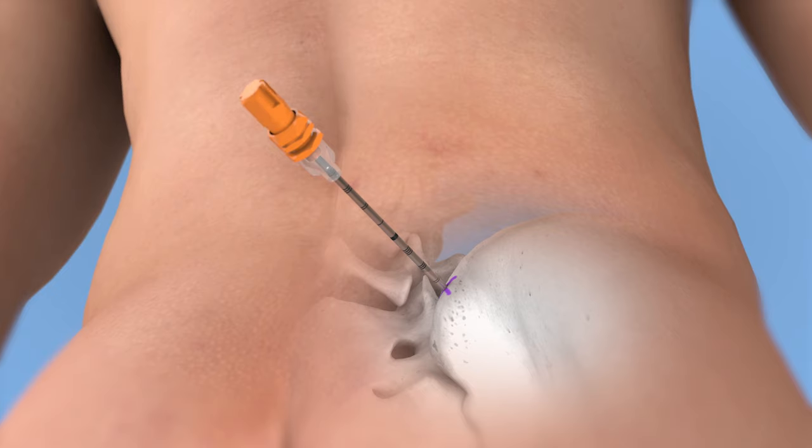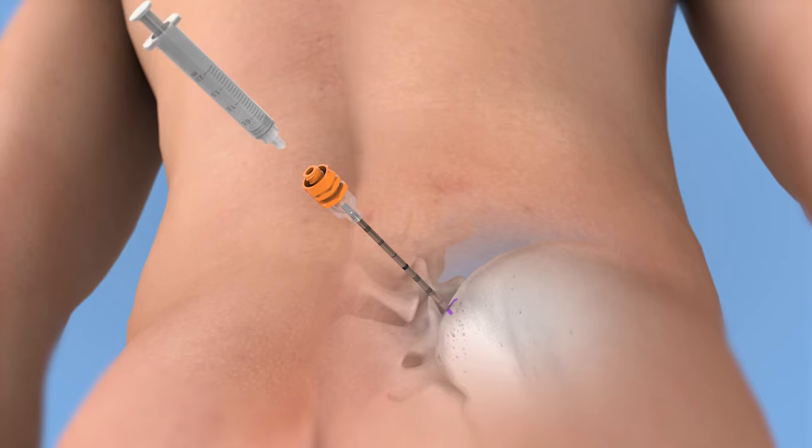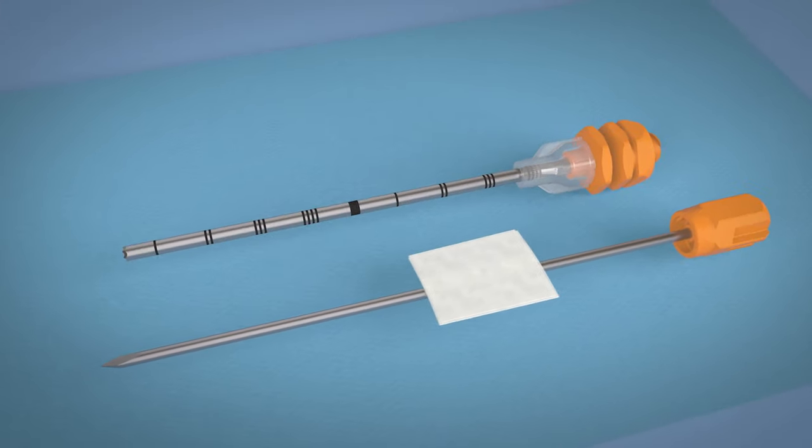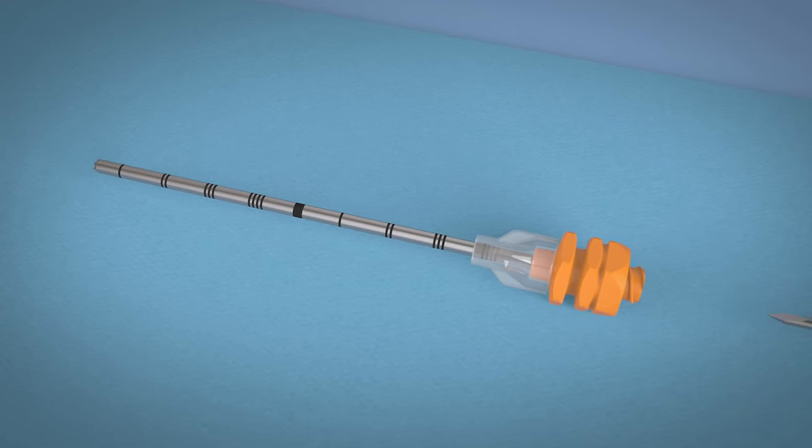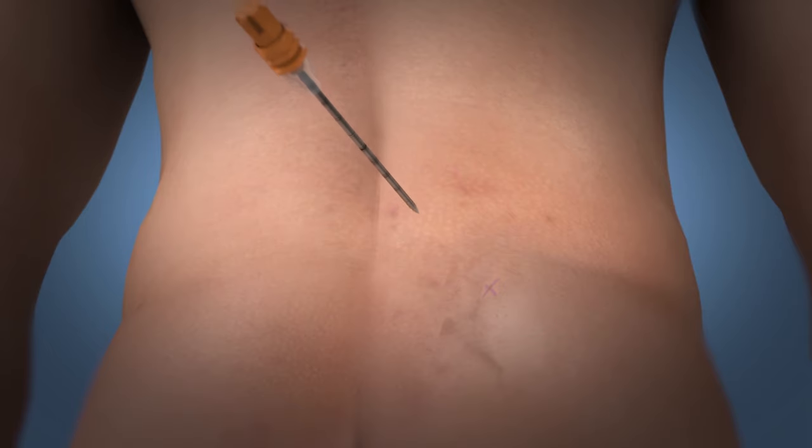Gently twist and lift the stylet out of the cannula. Attach a syringe and aspirate volumes ordered. Remove the cannula from the body with the driver or manually. Wipe off the stylet to remove any residue, re-insert stylet into cannula and tighten to ensure the stylet is fully in the cannula. Manually insert the needle into the prior skin insertion to the level of periosteum, slightly redirecting the needle to an adjacent location of the previous insertion site.